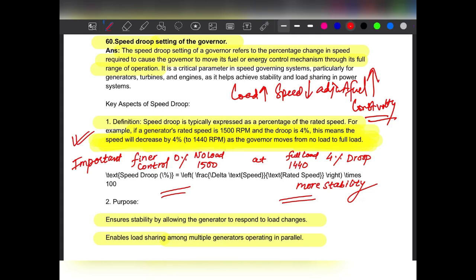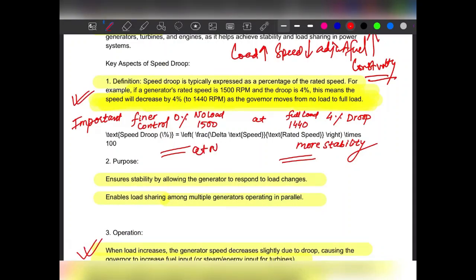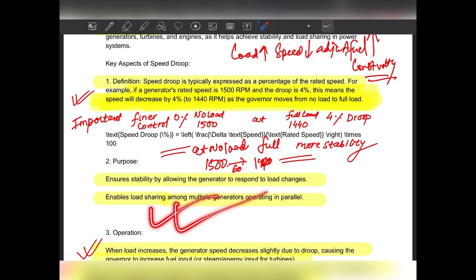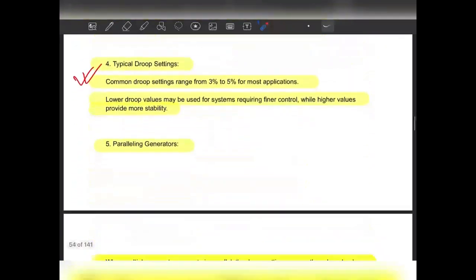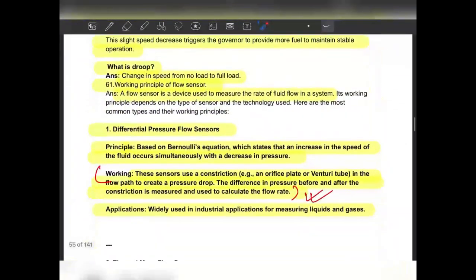It means at no load your engine RPM will be 1500 RPM, and when you run this generator at full load, your full load RPM will be 1440. It will drop by 60 RPM from no load to full load. That is basically droop. Okay, so you understand this very well. Just read this one. Finish. So move on to the next.